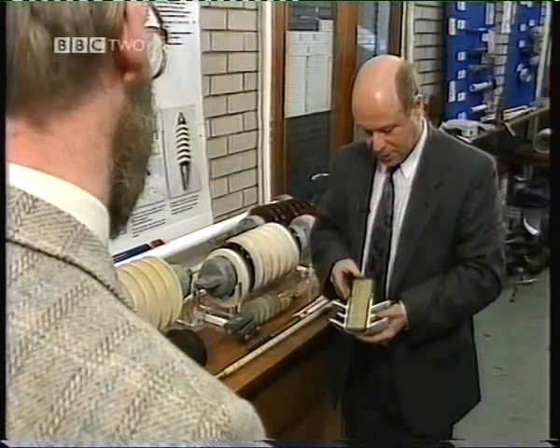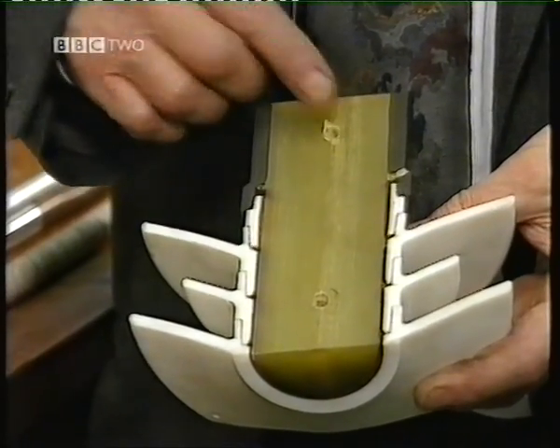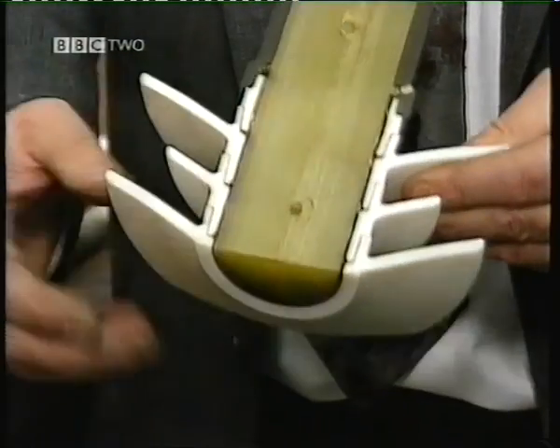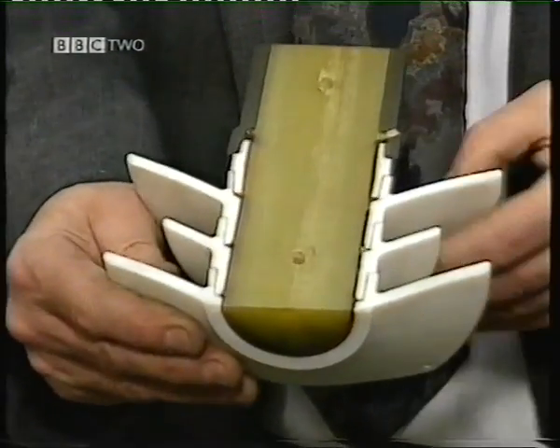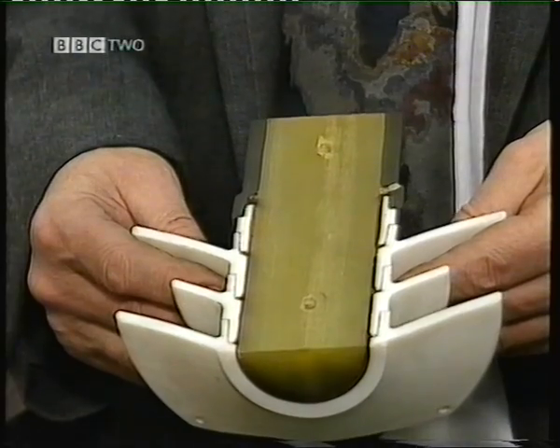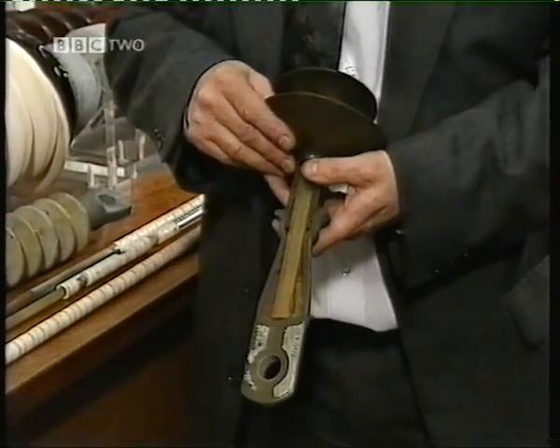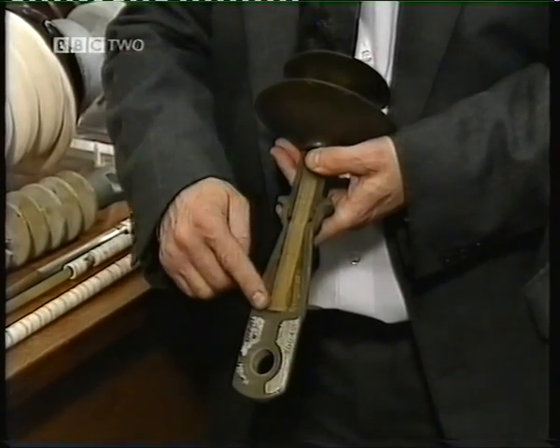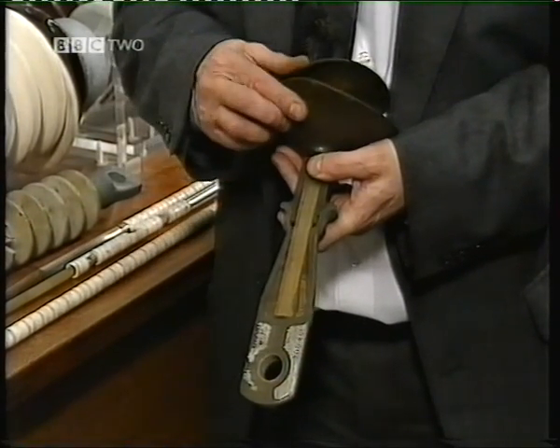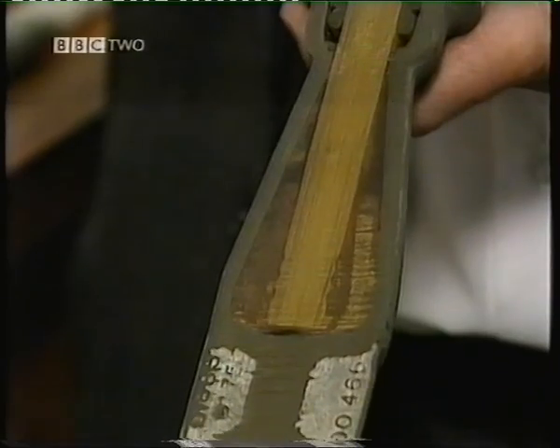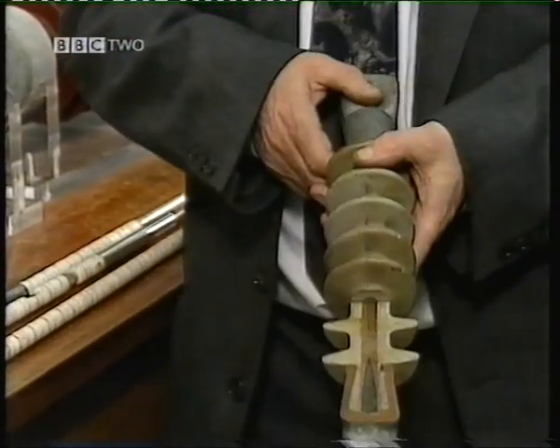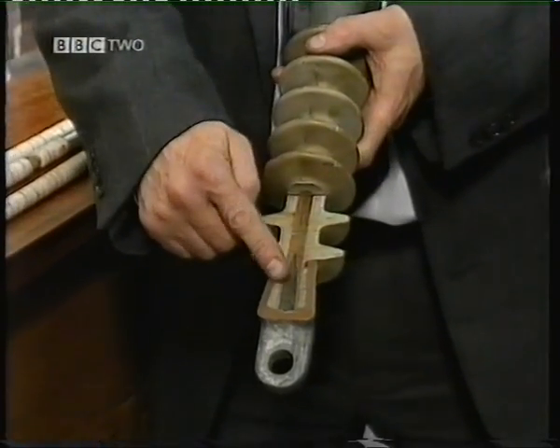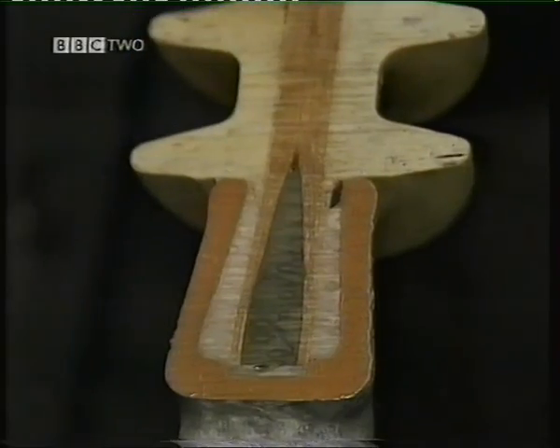Polymeric insulators consist of a glass fibre pultruded core with pre-moulded, in this case Teflon sheds, but many insulators have rubber sheds. This shows how the end fittings are connected to a glass fibre rod. In this case it's a bonded resin connection, and in this case the glass fibre has been split to provide a wedge to key into the end fitting.